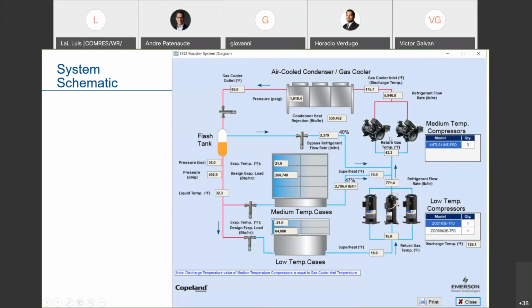But a nice feature that the software does, it says your entire refrigerant mass flow in pounds per hour is close to 6,000. But it also shows, hey, at 85-degree gas cooler outlet, you're going to be bypassing 40% of your mass flow into the medium temp to assure the proper flash tank pressure. So you think about that. 40% of your mass flow is being diverted into your medium temp, that these compressors must handle that load without any useful refrigeration happening. It's a price you need to pay with this architecture in order to do that.